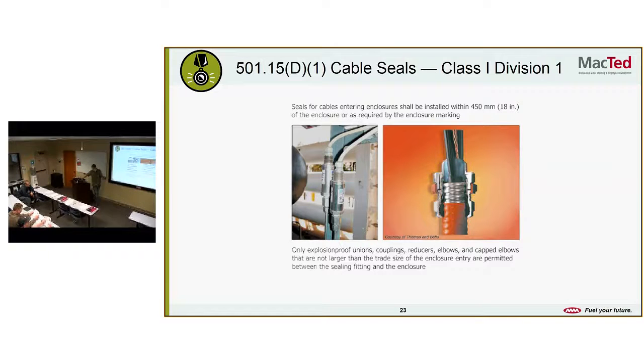Cable seals, Class 1, Division 1. Seals for cables entering enclosures shall be installed within 18 inches of the enclosure or as required by the enclosure marking. Only explosion-proof unions, couplings, reducers, elbows, and capped elbows that are not larger than the trade size of the enclosure entry are permitted between the sealing fitting and the enclosure.